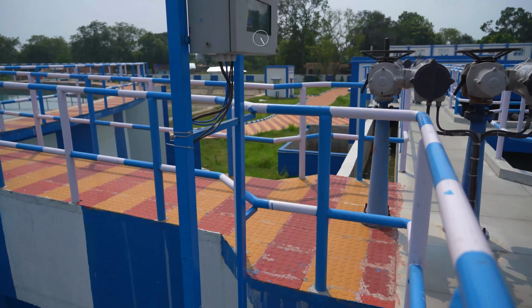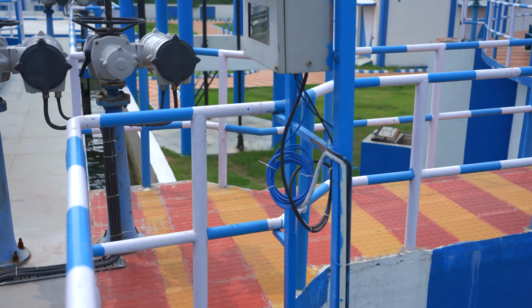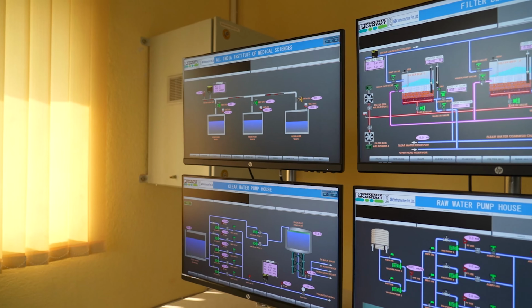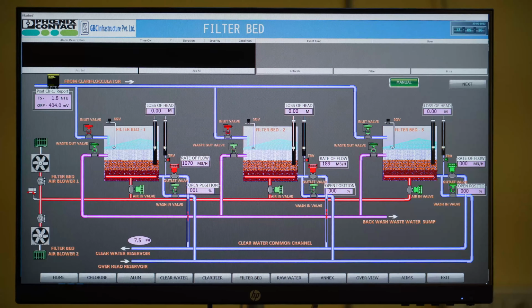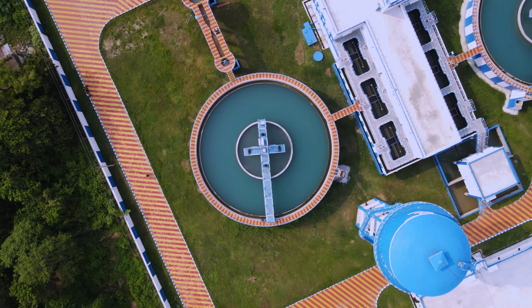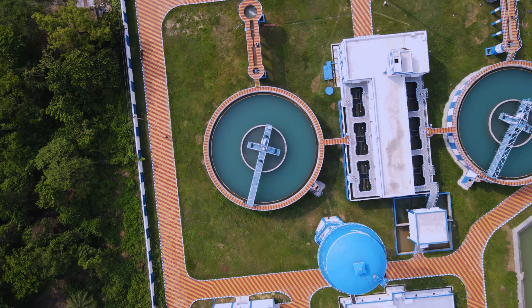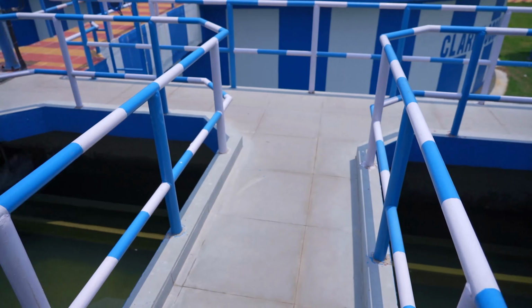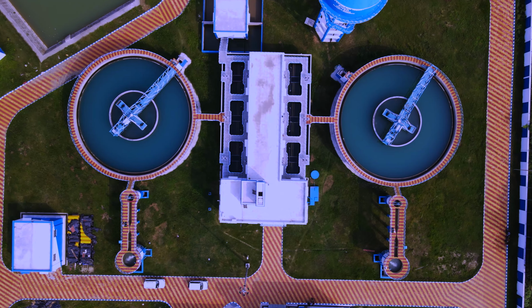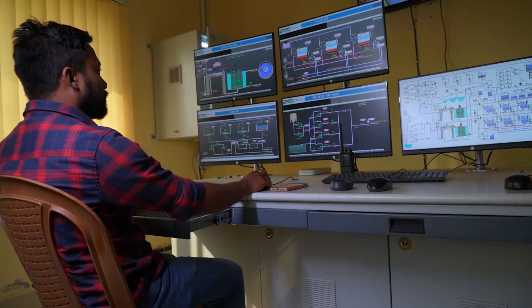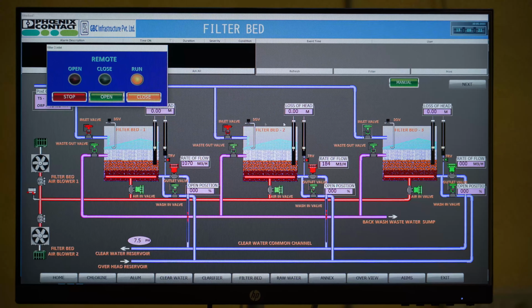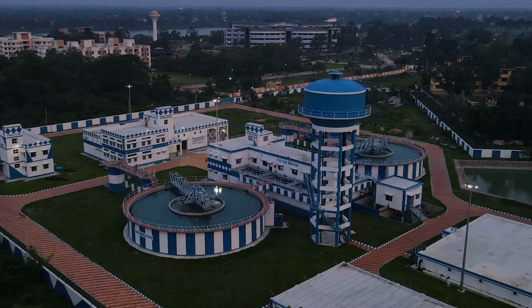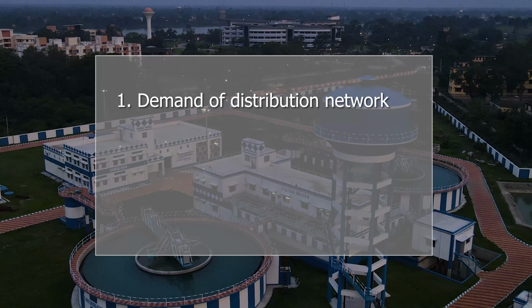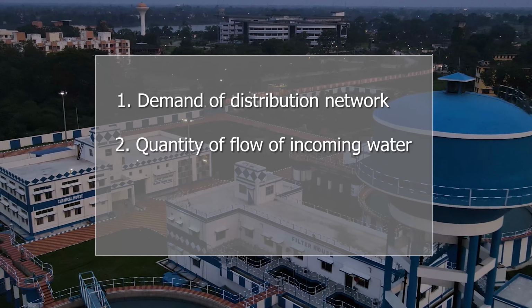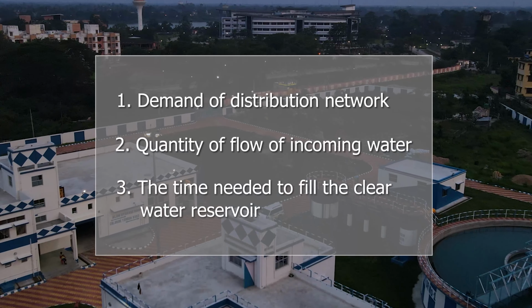Simultaneously through a common channel from both sides of the filter house. The online ORP meter and turbidity sensor installed on both sides of the common channel measure the quality of post-clarified water, which are valuable information for optimization of chemical consumption and indication of successful flocculation. There are 6 sand beds in the filter house, 3 each on either side of the filter house. The operator selects the filter bed according to the runtime schedule, which is pre-decided for the day. Selection of number of operating beds depends on demand of distribution network, quantity of flow of incoming water, and the time needed to fill the clear water reservoir.